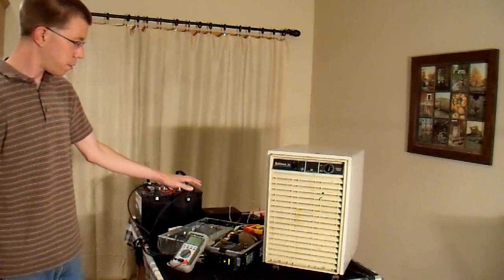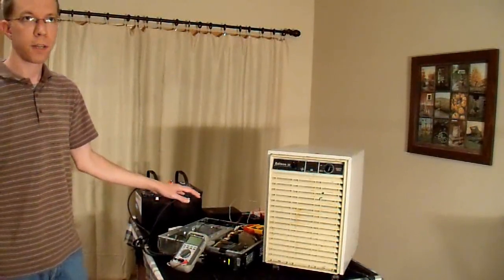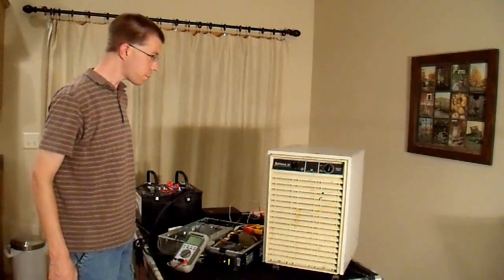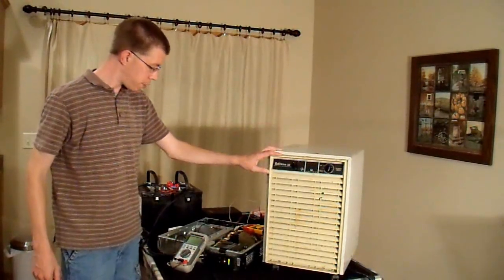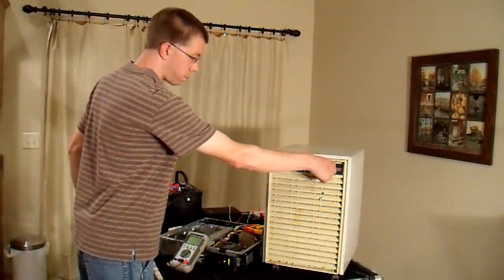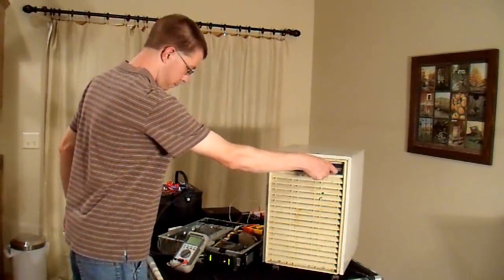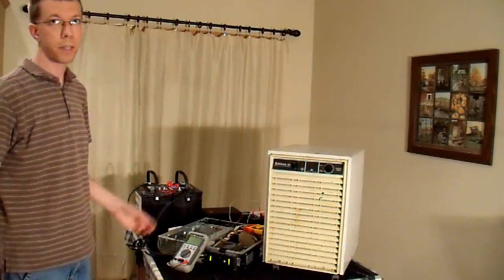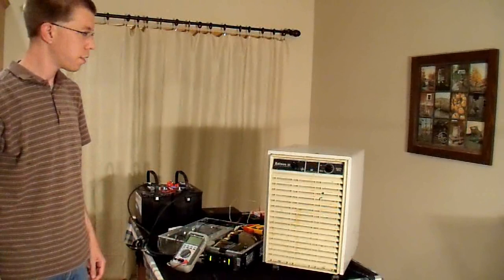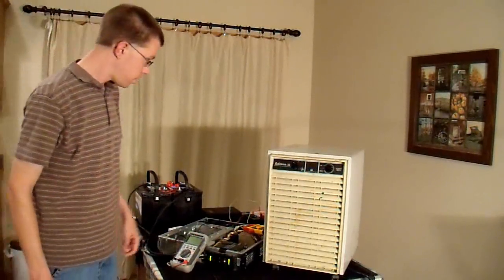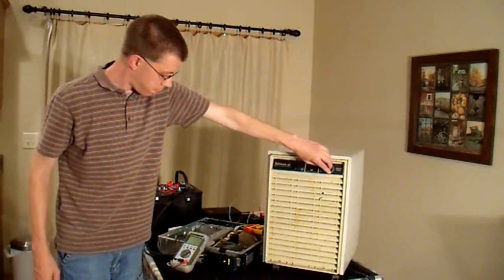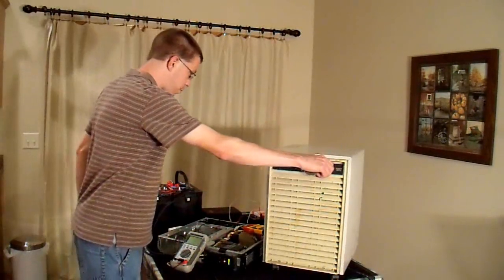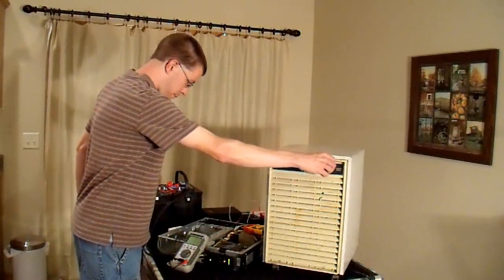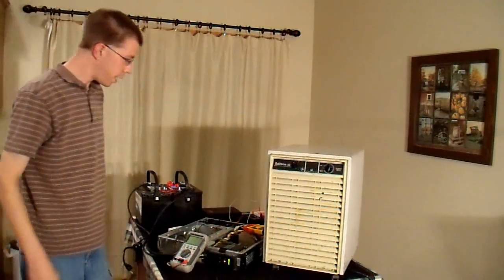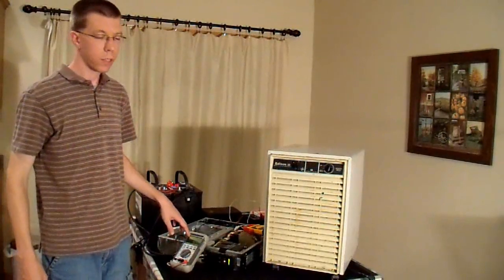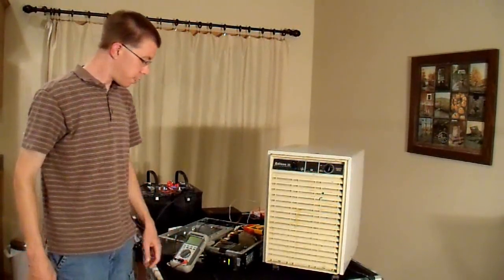So this UPS will not shut down even with a severe overload for about 2 seconds. That's how these are set up. So I'm going to do the same thing with the dehumidifier now. First I'll turn it on. And it does start this dehumidifier even in its stock configuration, which is kind of impressive. I didn't really expect that. But I'll shut it off. Let the pressure not equalize and turn it on briefly. And I get about 20 amps at 80 volts. So it is not able to supply as much power as the wall.